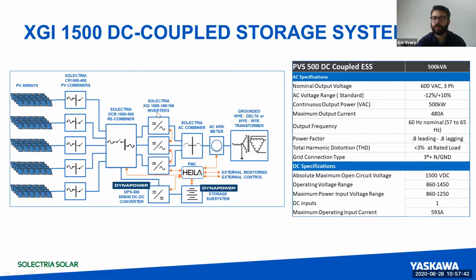And by doing so, it builds some resiliency into the system. If we have a power electronics failure in one inverter, we still have the other 2 inverters able to operate. Even if we had a double power electronics failure, with 2 inverters down, that 3rd inverter can still provide some capacity. So for a lot of these customers looking to do demand charge management, or even the clean peak standard, or something where the finances for the month hinge on discharging your batteries in an hour or less time frame, that 1 hour out of 30 days is your goal to hit your financial target for the month.